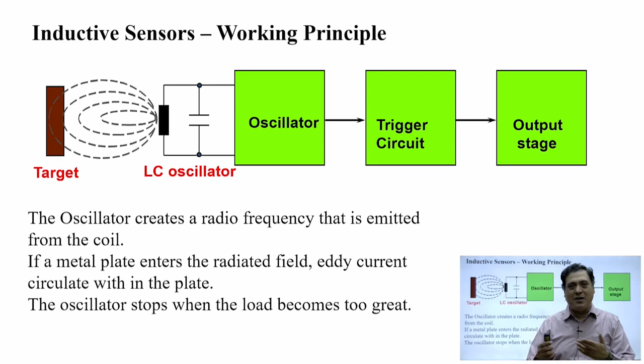We have all studied Lenz's law, which says any metallic target which has a current flowing through it will produce an electromagnetic field. On the same concept, eddy currents start producing in the target material. These eddy currents produce their own electromagnetic field, which opposes the field of the sensor. As a result, the oscillator stops oscillating when the load becomes very high. That means the electromagnetic field produced in the target material is so high that it opposes the field of the sensor and kills it altogether. This change of state, where the oscillator which was oscillating earlier has stopped oscillating, is captured by a trigger circuit, which then generates an output which we can take in a measurable form into our PLCs or controllers.